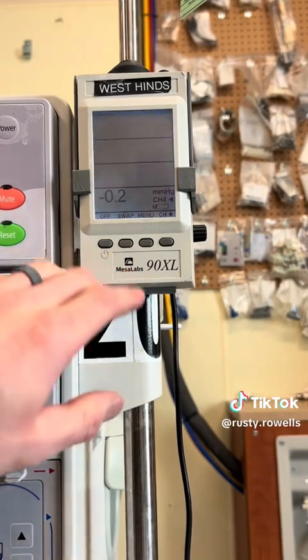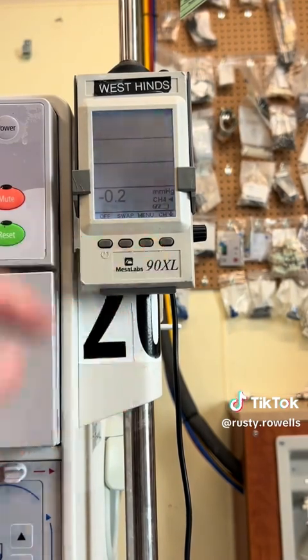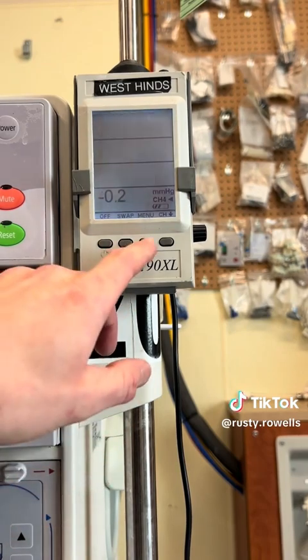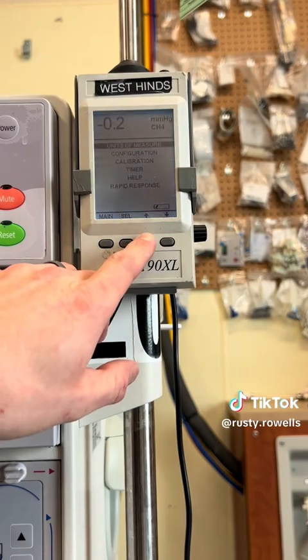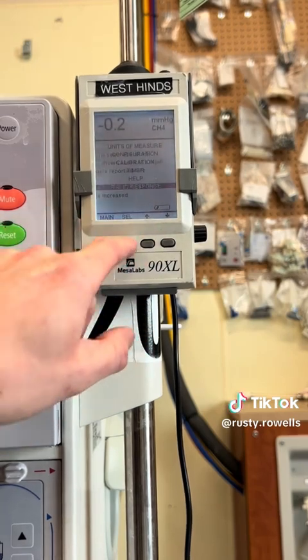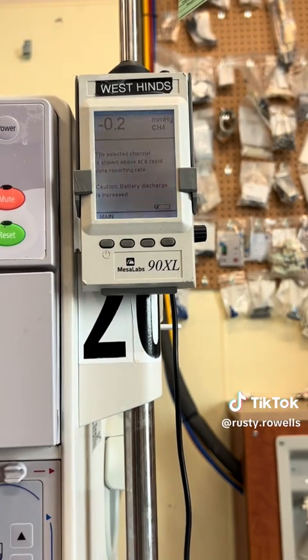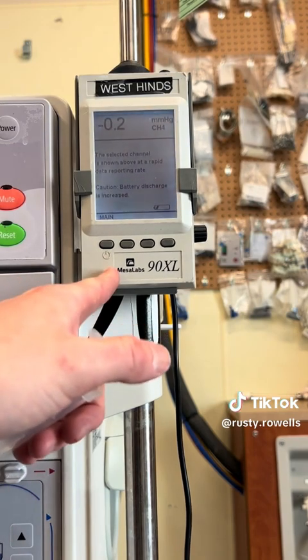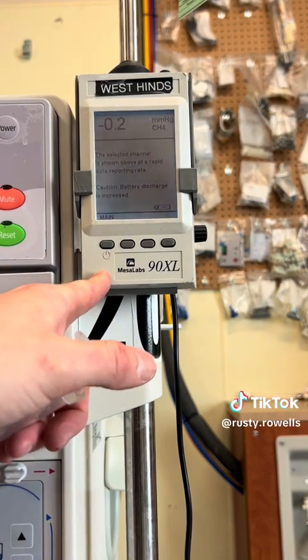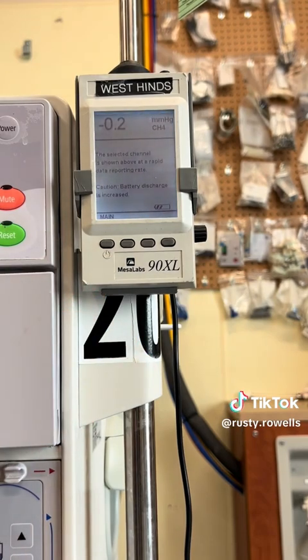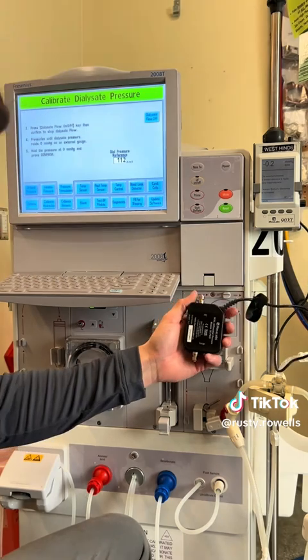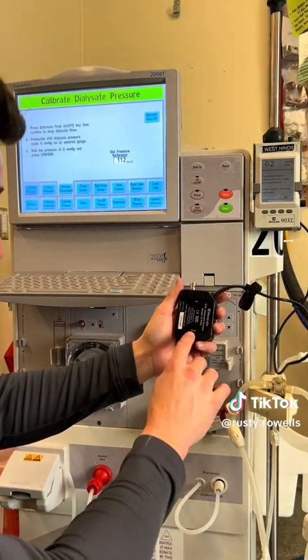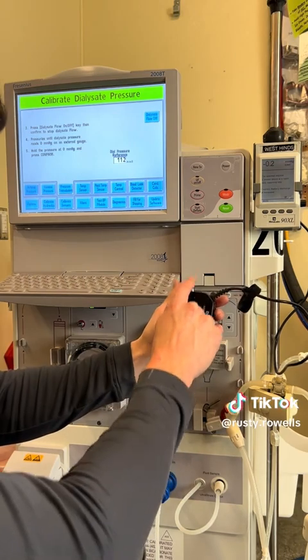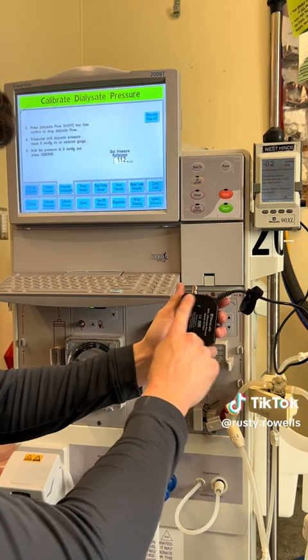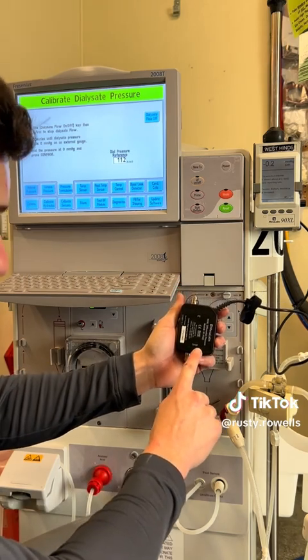All right, so looking at the 90XL, what I always like to do is put my meter in rapid response. So you go to menu, scroll down to rapid response, and then select it. What that's going to do is give you a more real-time reading. It sucks up your battery on your meter, but it gives you a more real-time reading and you can be more accurate when calibrating pressures. This is our pressure module right here. So you have a gauge side and you have a ref side. Do not hook up to the ref side. You need to always hook up to the gauge side.